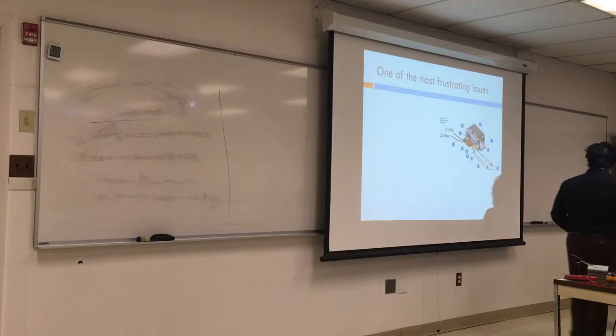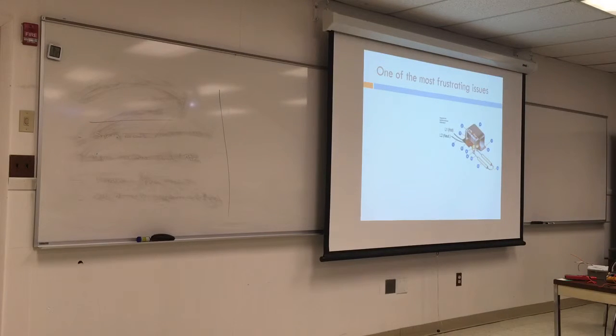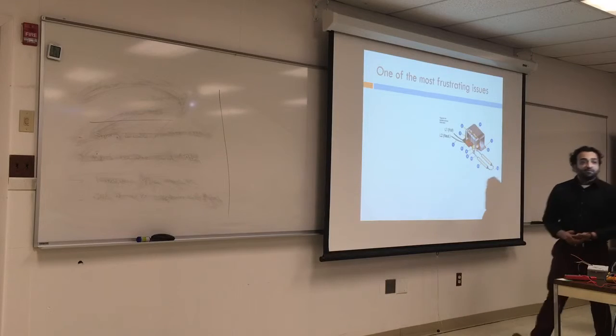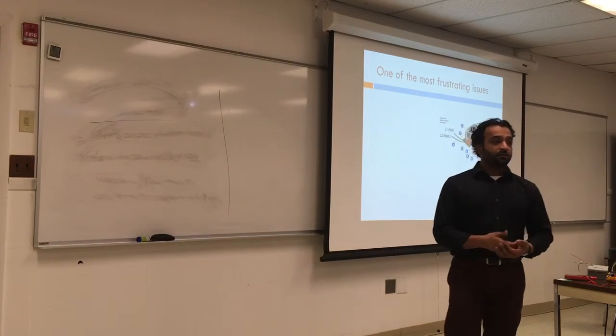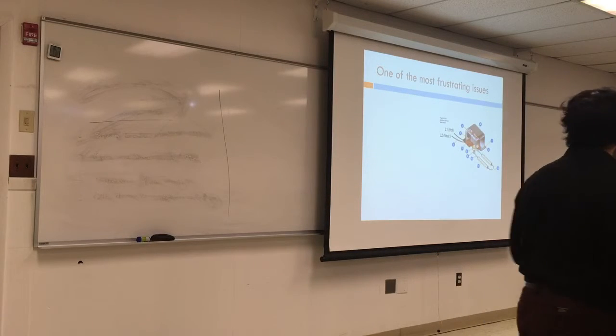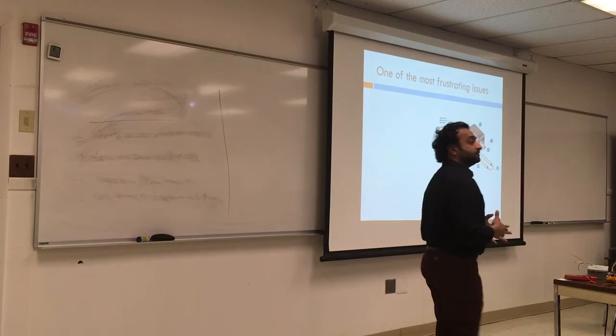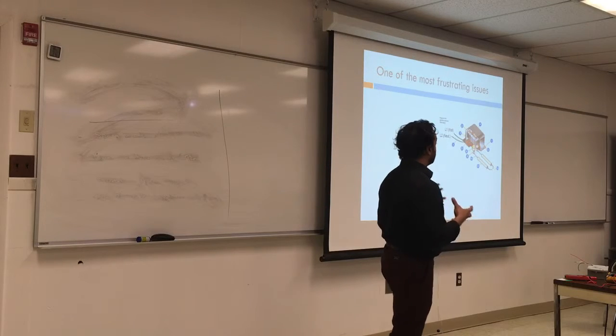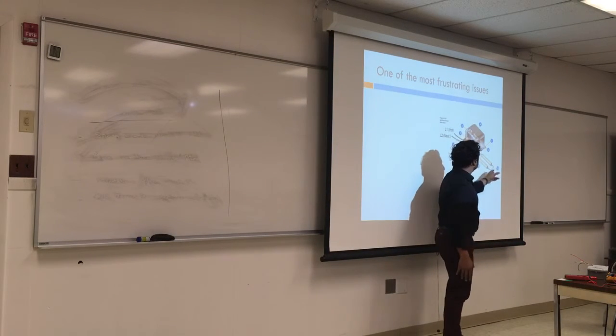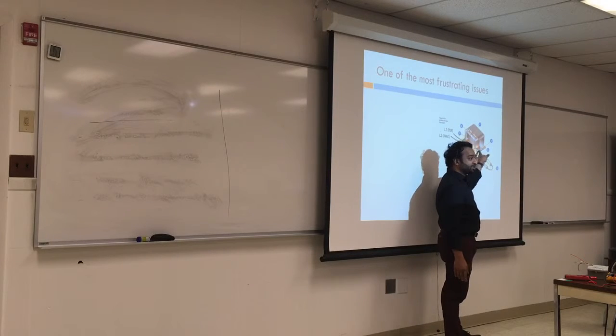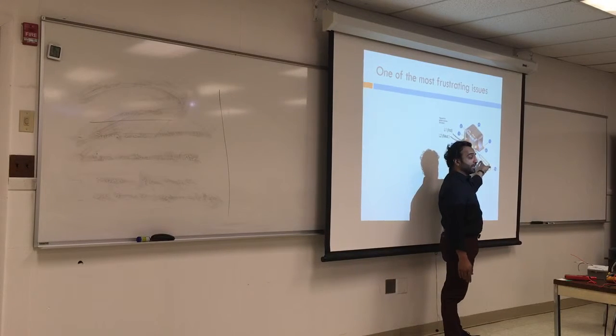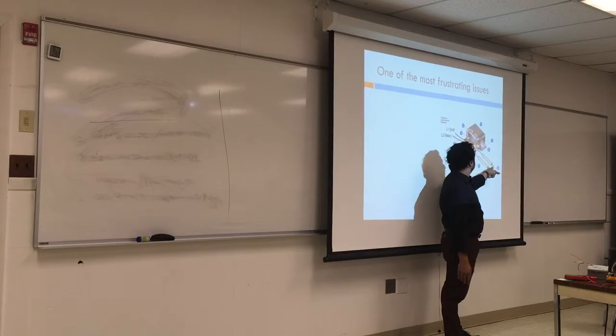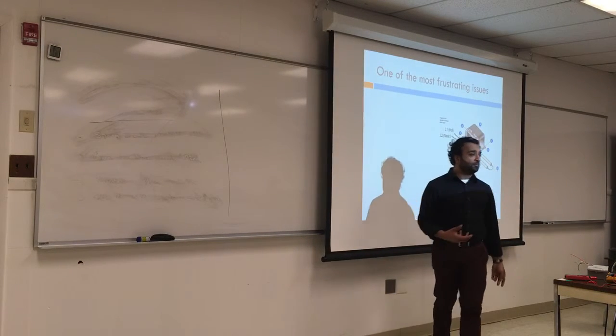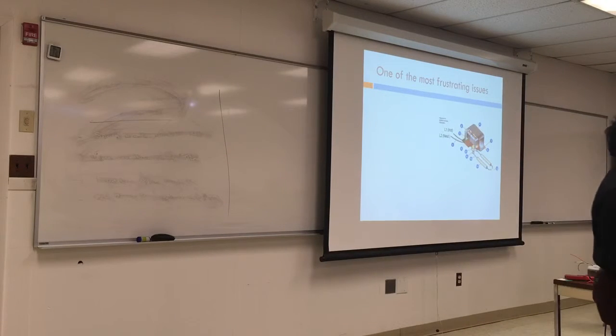It's one of the most frustrating issues because, again, so many things can go wrong. We keep trying to fix those issues. So this is what happens. You call for heat, the water turns on, and there is no flame, and the system goes into safety. So the first thing you have to make sure is happening is that the voltage is getting completely into the electrodes. If you see, you can be missing some connection here. This could be dirty. These could be misaligned. One of them is shorter than the other. So it will take you some time to just try to see why you have no ignition.